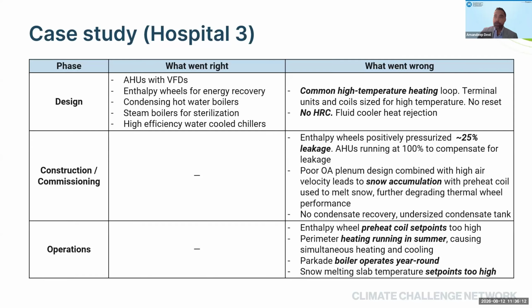As a result, they had to turn on extra air handling units, which should typically be used as redundant units, because they couldn't meet the air change rates with this configuration of the AHUs. Their systems are now running at a higher ventilation watts per CFM as a result. There were similar issues around the enthalpy wheels and AHUs working 24/7. The preheat set point on these coils was set too high, which basically disabled the heat wheels, and as a result they're not able to reclaim any of that waste heat in their system.